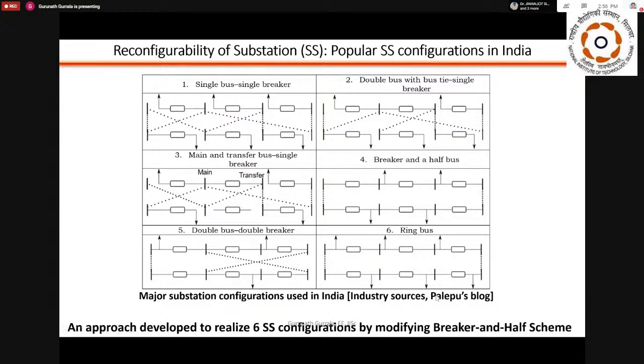So our goal is, at any point, if you go to a substation, there will be only one configuration. Like this particular one, say a double bus, it will be a double bus double breaker. But as a researcher, you should know how to protect all these systems. At least you should be experienced, or you may want to test some schemes specific to, say, breaker failure schemes. Then you need this configuration to be implemented.